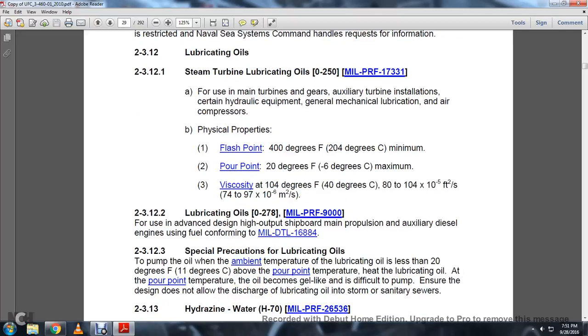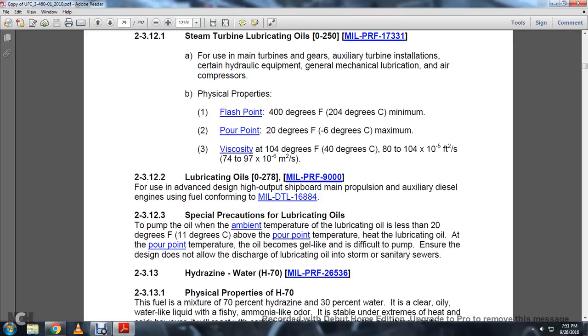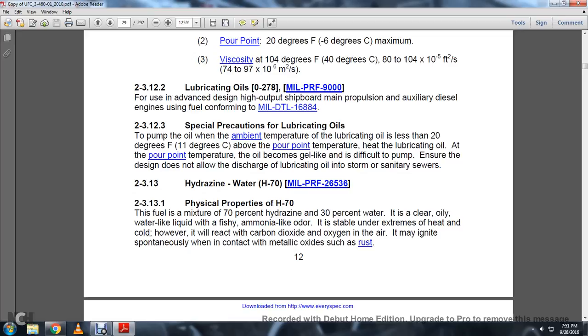2312-2 Lubricating oils for use in engines designed with high output shipboard main propulsion and auxiliary diesel engines using fuel conforming with the military detailed specification 16884. 2312-3 Special precautions for lubricating oils: to pump oil, the ambient temperature for lubricating oils should be less than 20 degrees Fahrenheit above the pour point temperature. Heating lubricating oil at pour point temperature, the oil becomes gel-like and difficult to pump. Ensure the design is not able to discharge the lubricating oil into the storm or sanitary sewers.